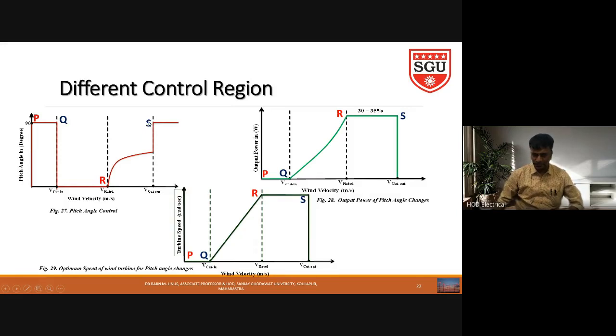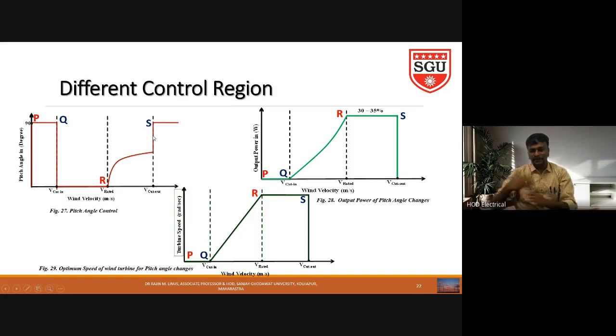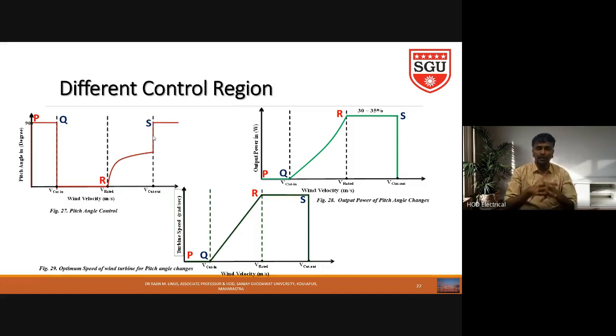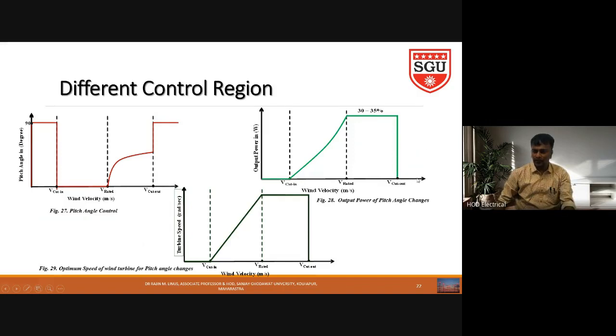At the point S, wind velocity reaches above the cutout wind speed, which is normally 25 m/s. From V_rated up to 25 m/s we can gradually increase the pitch angle. After cutout speed is exceeded, we again make pitch angle = 90 degrees, since the wind turbine cannot withstand wind velocity above 25 m/s. At pitch angle 90 degrees, all wind passes behind the turbine, and output power comes down to zero.